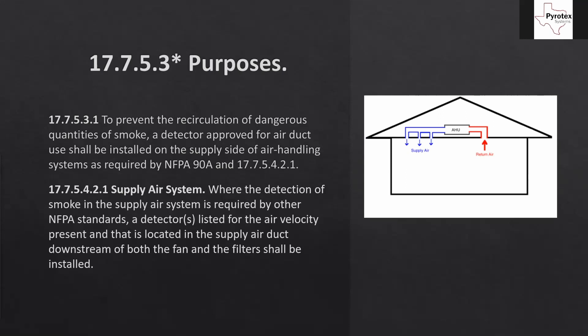Notice this section doesn't mention the 2000 CFM threshold we always reference, and doesn't cover the return side in detail — there's a small paragraph that basically just says when required by NFPA 90A, put a duct detector in the return side. On the right I have a picture of an AHU showing the supply and return sides, because this can get confusing. I remember it this way: the supply side is supplying conditioned air to the building, and the return air is returning back to the unit.